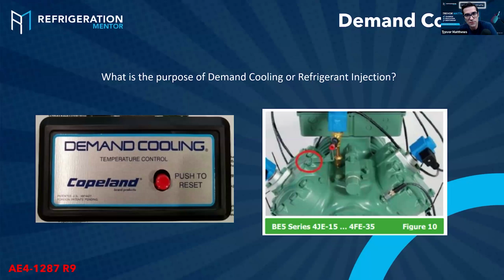It's like, hey, Trevor, I'm doing this retrofit, I'm adding this and that. Do I need to add demand cooling? If it's a low temp application, I just say yes. You know, if you need to pinch pennies and stuff, you've got to go in, and I'm going to show you tonight how to figure that out. Do you need demand cooling or not? Do you need refrigerant injection or not? Could you get away with a head cooling fan? It all depends. It all depends on that operation envelope.